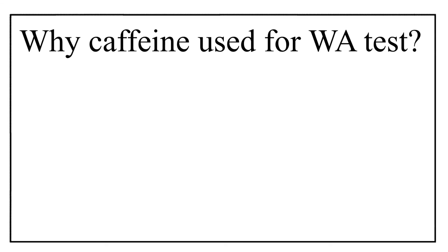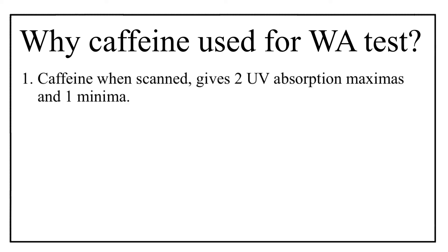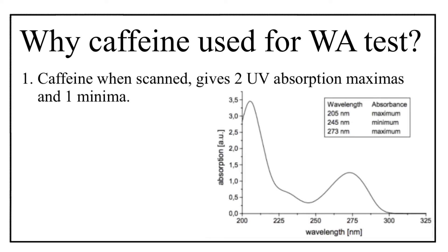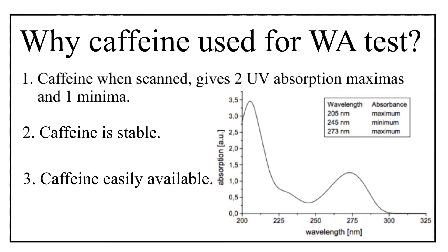There are three main reasons why caffeine is used for the wavelength accuracy test. Number one, caffeine solution when analyzed under UV gives two absorption maximas and one absorption minima, so its UV spectrum covers almost the entire UV range. Number two, caffeine is very stable. Number three, caffeine is easily available in the market. These are the three reasons caffeine is used for the wavelength accuracy test.